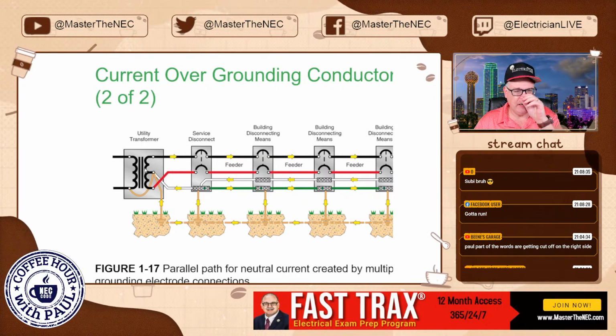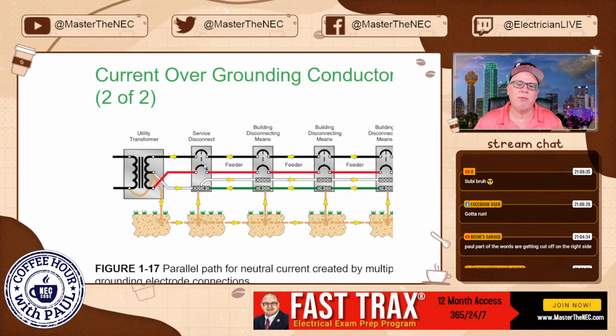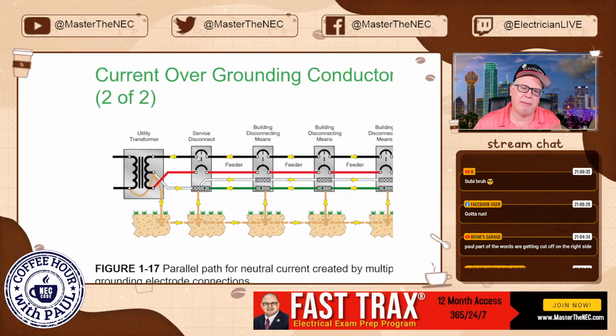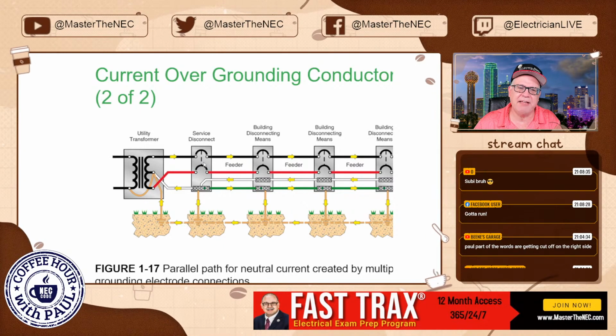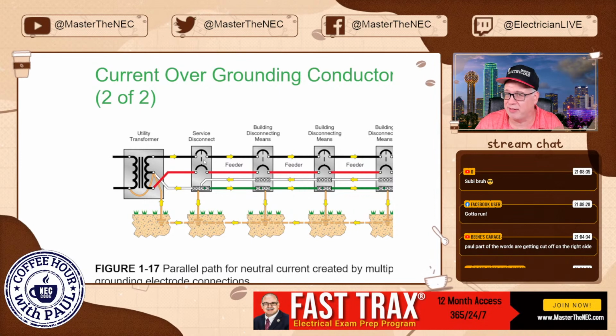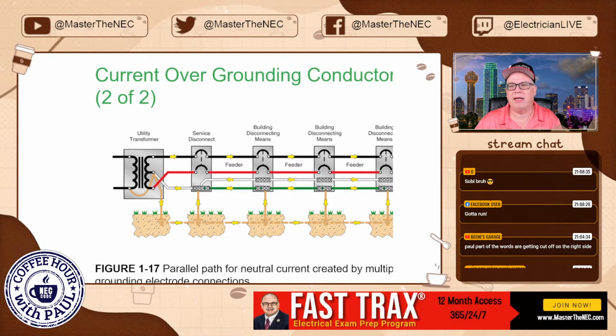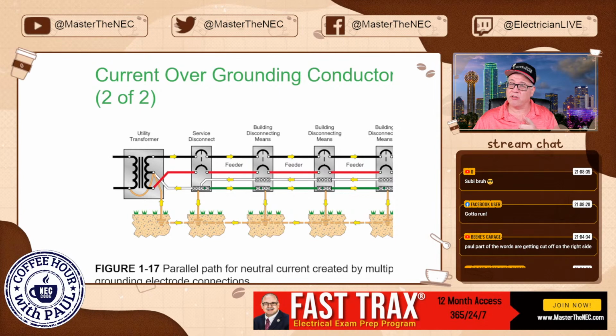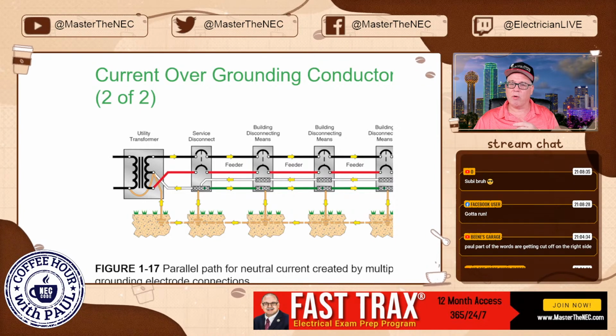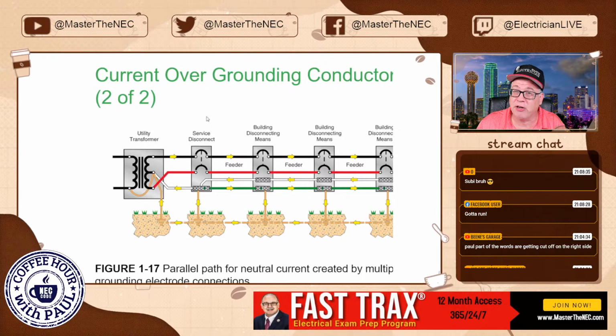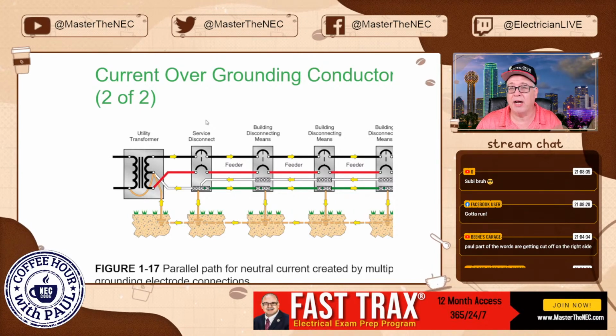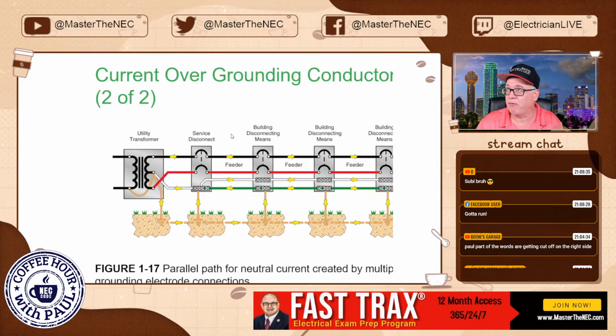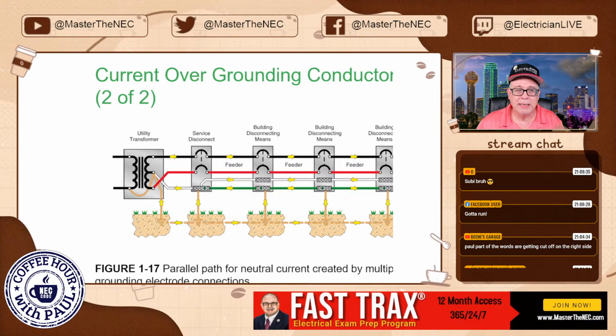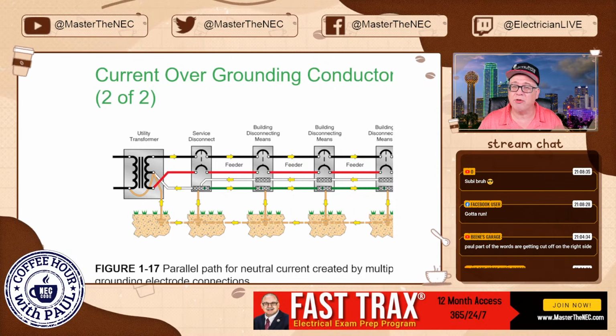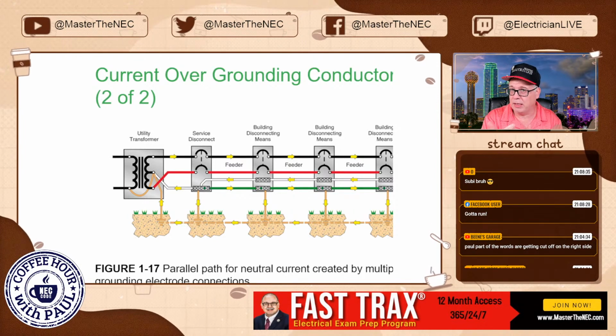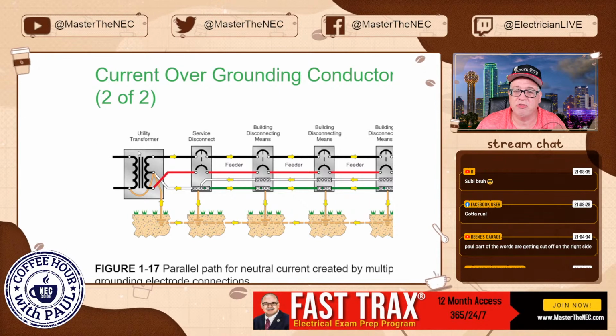So look at this example. Here's our utility. Here's our service disconnect, and we've broken it all out. So this could be an example of maybe 230.85. This is the service disconnect, an emergency disconnect that's required for a 1 and 2 family dwelling in the 2020 code. Hey, did you know that in the 2023 code, this is also now required? Emergency disconnect is also going to now be required for feeders to dwelling units. Now you do. So that's a change, and I can't remember if it's 225.41 or 42, but subscribe to my Instagram and you'll see a lot of new changes that are coming when it comes to the 2023 code, and I'm sharing them with you.